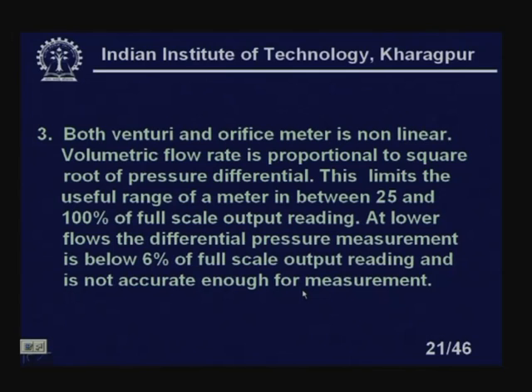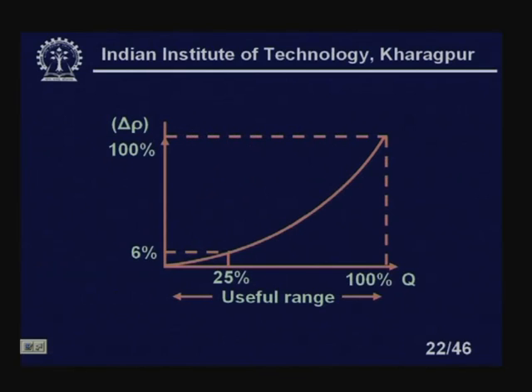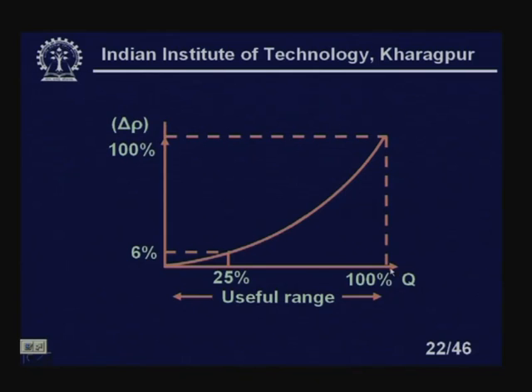Both venturi and orifice meters are non-linear — the volumetric flow rate is proportional to the square root of the pressure differential. This limits the useful range of the meter to between 25 and 100 percent of full scale output reading. At lower flows, the differential pressure measurement is below 6 percent of full scale output and is not accurate enough. The error is quite high at low flow velocities and low at high flow velocities.